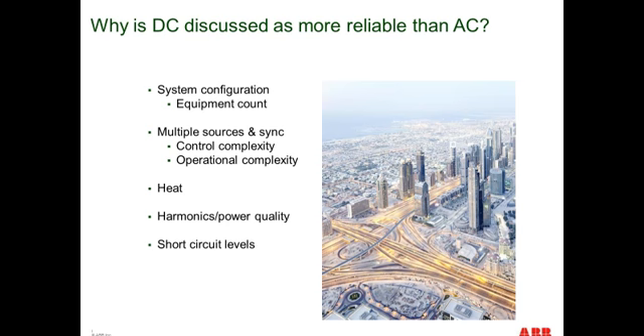Perhaps another issue might be power quality and harmonics, where if you were able to reduce the number or size of VFDs, or possibly implement DC motors in your system to alleviate the need for harmonic correction or dampening, this could be conceived as a reliability improvement. Today we see designs with fault currents in the 100 to 150 and 200 KAIC range. So if it's possible to lower those levels, you could be better assured that your overcurrent protective devices are going to open and safely clear any fault condition, and not risk opening catastrophically.